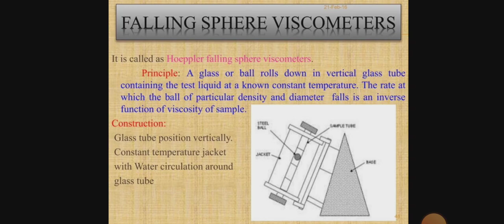Working: a glass or steel ball is dropped into the liquid and allowed to reach equilibrium with the temperature of the outer jacket. The tube with jacket is then inverted so that the ball is at the top of the inner glass tube. The time taken by the ball to fall between two marks is measured. The process is repeated several times to get concurrent results. For better results, select a ball that takes NLT 30 seconds to fall between two marks.